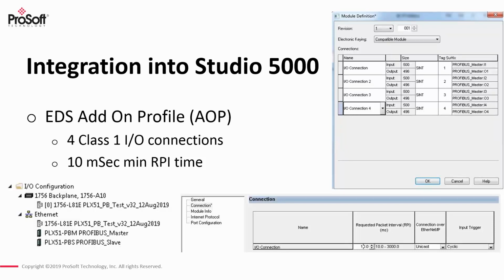So when we talk about the integration into Studio 5000, this is done using an EDS add-on profile. And so as you can see, you can define up to 4 Class 1 I/O connections, each one of those with a maximum size of 500 bytes of input data, 496 bytes of output data. So this is what allows us to transfer all 1,536 bytes of Profibus data over a high-speed Class 1 I/O connection back into an Ethernet IP processor. And each of those I/O connections can be specified as low as a 10 millisecond RPI time.